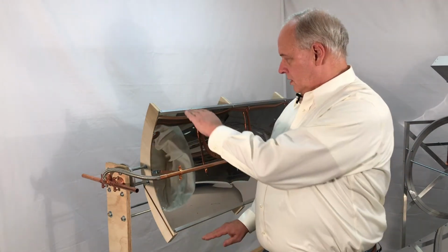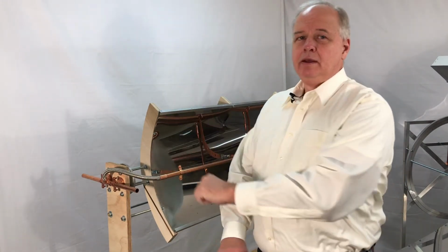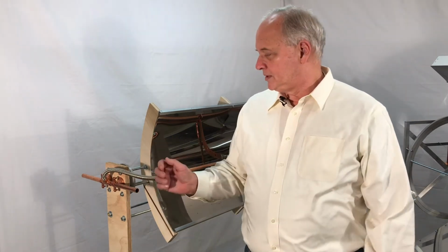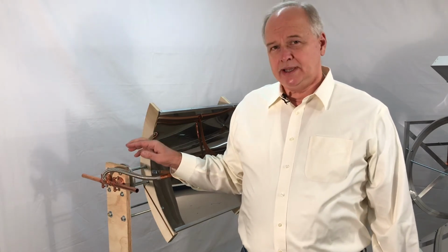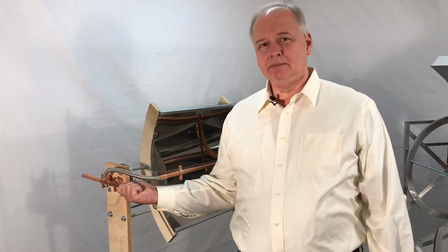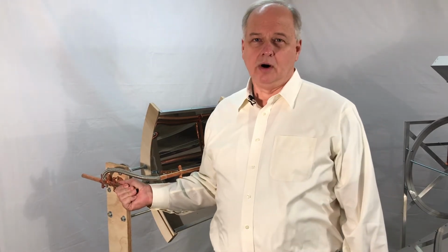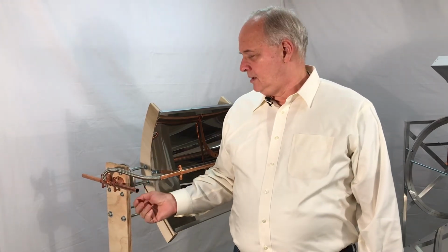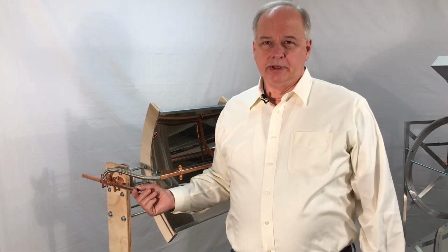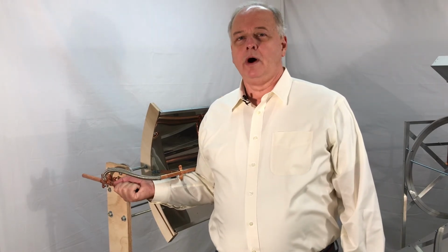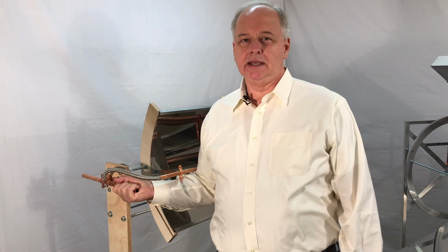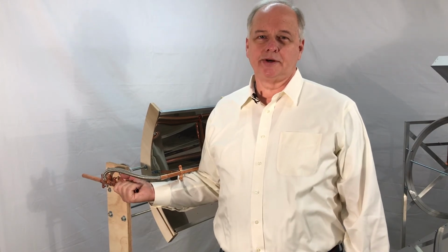In summary, current trough apertures are limited to 23 feet, or about 6.77 meters. They have flexible connections, which limit the thermal fluid to synthetic oil. Transferring the heat from the oil to generate steam results in a 15% loss of energy and efficiency. The synthetic oil has an upper temperature limit beyond which decomposition accelerates.